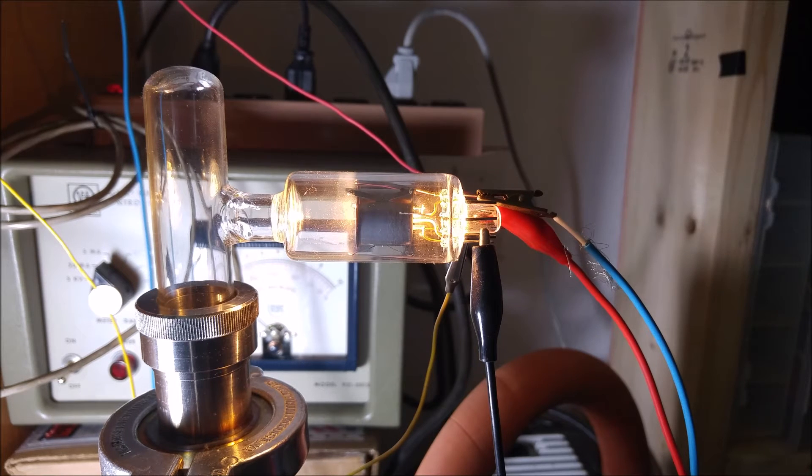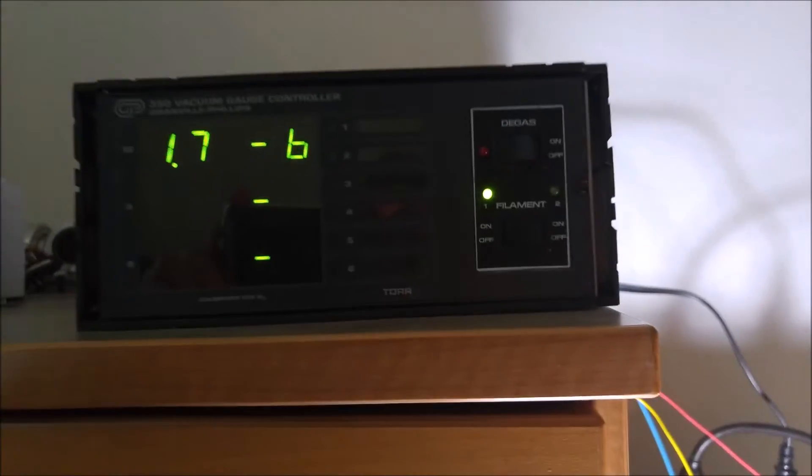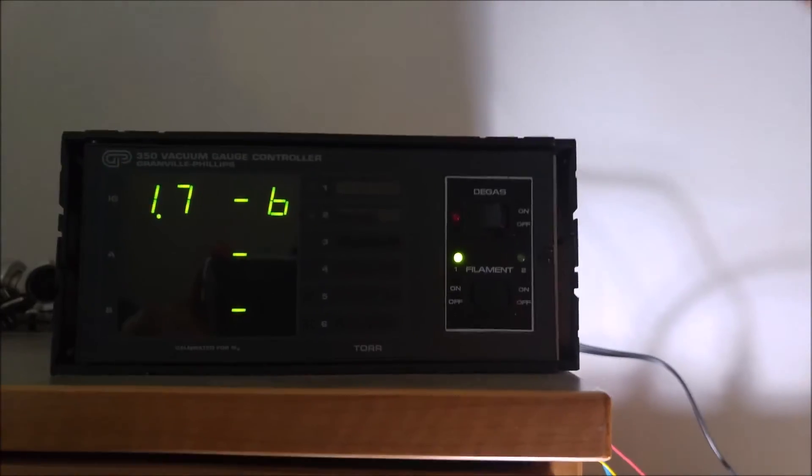First, let's talk about what an ion gauge is and what it does. An ion gauge is an instrument used to measure levels of high vacuum, from about 1 times 10 to the negative 3rd torr to 1 times 10 to the negative 8th torr. Newer gauges can read even lower amounts.